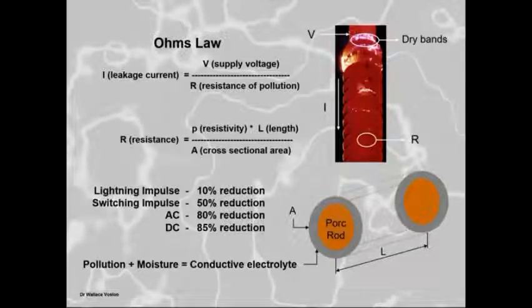There you can see some dry bands. This is on an insulator. I took the photo with a normal standard camera with 1000 ASA film with a 3-minute exposure and a red flashlight. Then you can beautifully see the actual discharge activity. This was on a post insulator I tested at one of my test stations. Now, you find that the current here is determined by the resistance of this.